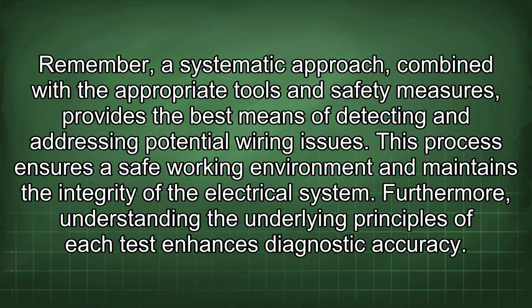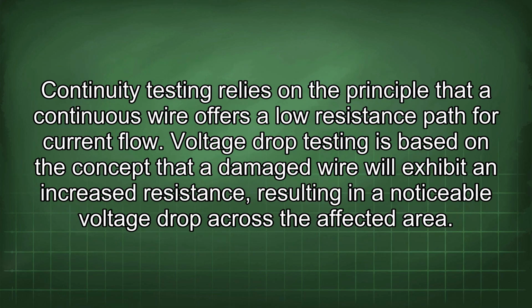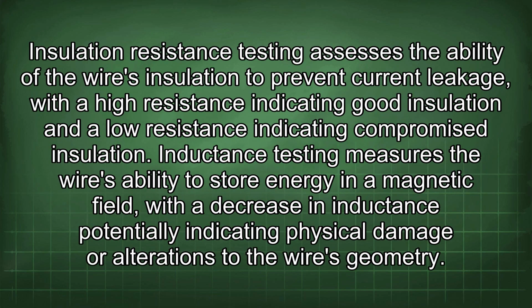Furthermore, understanding the underlying principles of each test enhances diagnostic accuracy. Continuity testing relies on the principle that a continuous wire offers a low resistance path for current flow. Voltage drop testing is based on the concept that a damaged wire will exhibit an increased resistance, resulting in a noticeable voltage drop across the affected area. Insulation resistance testing assesses the ability of the wire's insulation to prevent current leakage, with a high resistance indicating good insulation and a low resistance indicating compromised insulation. Inductance testing measures the wire's ability to store energy in a magnetic field, with a decrease in inductance potentially indicating physical damage or alterations to the wire's geometry.